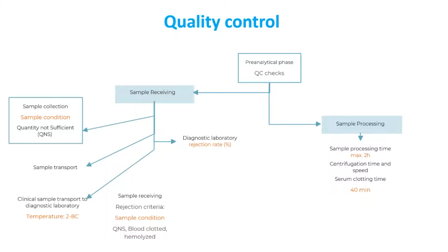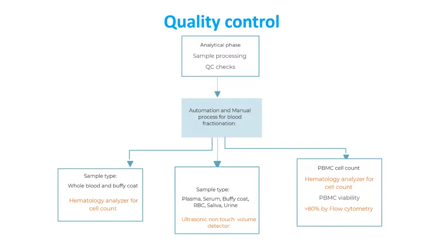In the analytical phase, we also have some quality checks. Our process starts with initial fractionation, automated or manual, and we needed some quality checks. To measure the white blood cell count, we use a hematology analyzer for cell count, and also for peripheral blood mononuclear cells, we use the hematology analyzer for cell blood count, and also another method, the flow cytometer, to measure cell viability. Then, to detect that the volume is dispensed accurately by the machine, or fractionated accurately by personnel, we have a volume detector.